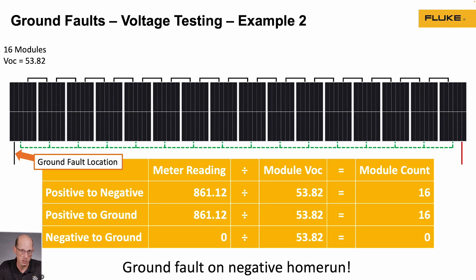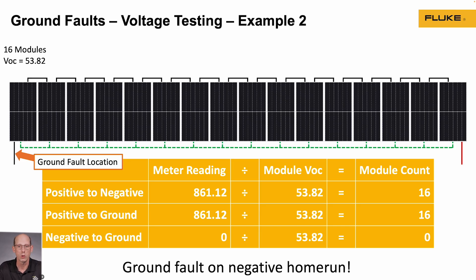Negative to ground measured zero volts, which is the reading I expected. This indicates there are zero modules between the negative end of the string and the ground fault, and 16 modules between the positive end and the ground fault. That means the ground fault is in the negative home run wire from the end of the string going back to either the combiner box or the inverter. This is a frequent fault location that's easy to miss — when you're used to seeing open circuit voltage of the string as zero, it can be easy to overlook that the positive to ground reading was 861 volts, not zero. Keep this in mind so you don't miss ground faults on the positive or negative home run wires.